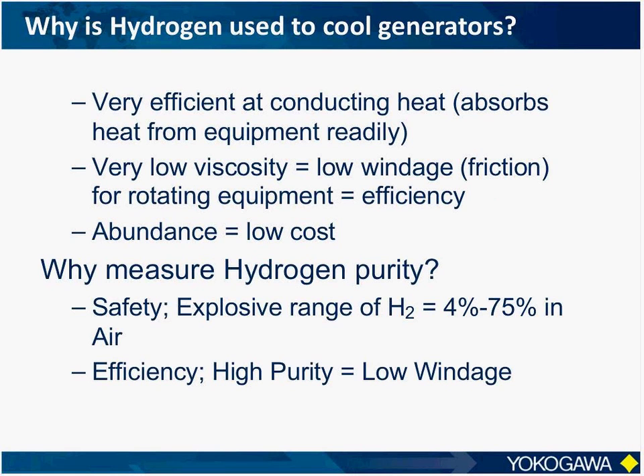First, a little background on why hydrogen is used to cool power generators. Hydrogen is very efficient at conducting heat, which means it'll readily absorb heat from the equipment that is to be cooled. Hydrogen has a very low viscosity compared to other gases, and that low viscosity means less friction or windage will be created by the rotating equipment, and this allows the electricity to be generated more efficiently. Also, hydrogen is one of the most abundant substances on Earth, which translates to relatively low procurement costs.